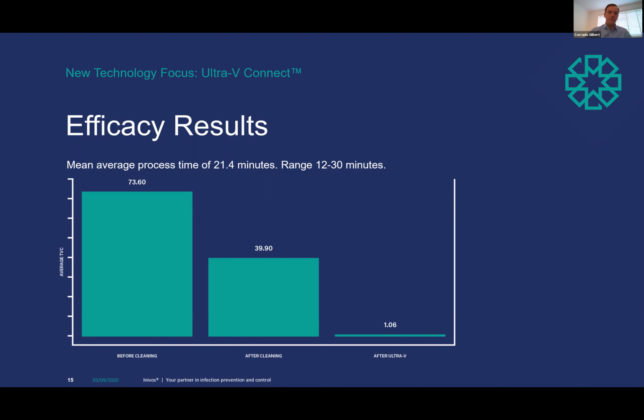So after a decontamination process with UVC, what we've always emphasized and continue to emphasize is the importance of the validation, because of the 2 key drawbacks. Due to it being a line of sight technology and it works on the power of the inverse square, we must know exactly what's going on in the room at any point during the process, so that once the process is complete, the hospital's got the assurance of a validated, successful decontamination process at every point around the room.